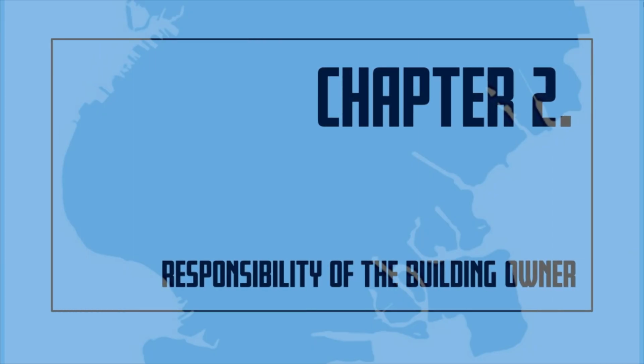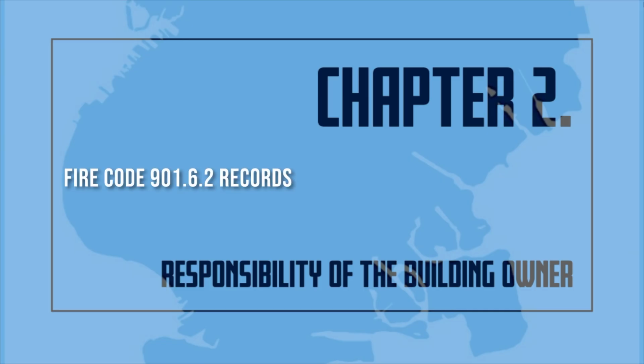Chapter 2. Responsibility of the building owner. It shall be the owner's responsibility to maintain the sprinkler system and to determine the individual qualifications and competencies of the individual, the certificate of fitness holder, to perform certain functions related to inspection, testing, and maintenance. Fire Code 901.6.2. Records. Records of all system inspections, tests, servicing, and other maintenance required by this code, the rules or the reference standards shall be maintained on the premises for a minimum of 3 years and made available for inspection by any department representative.